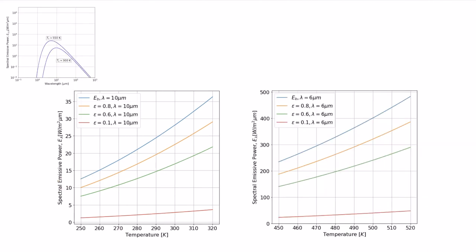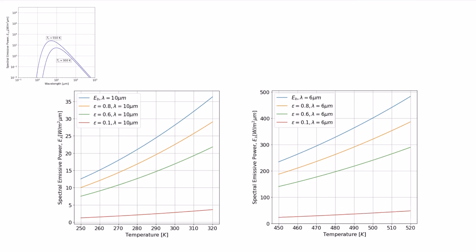Your thermal camera has multiple ranges. If we look at an object at 300 Kelvin or room temperature, there's a rather different distribution than if I increase that by 250 degrees to 550 Kelvin. With this logarithmic scale, these emissive powers are about an order of magnitude higher at 550 Kelvin. This is the same response at 6 micrometers around that 500 Kelvin range. A low emissivity object is going to be very hard to get an accurate reading of. This curve is almost flat, and it's very different than the higher emissivity ones, so it will affect our reading substantially. This is why cameras will warn you that it's very difficult to get readings on low emissivity objects.